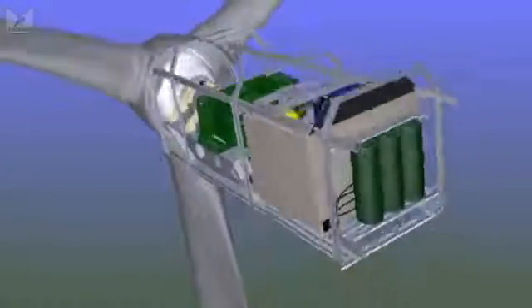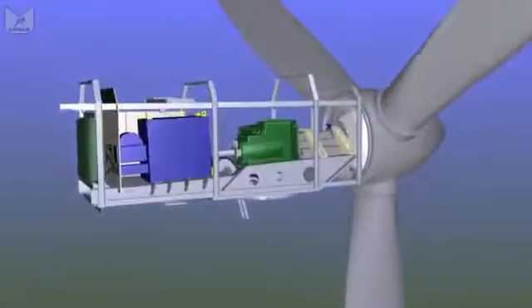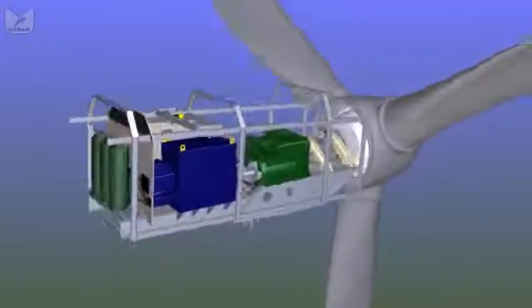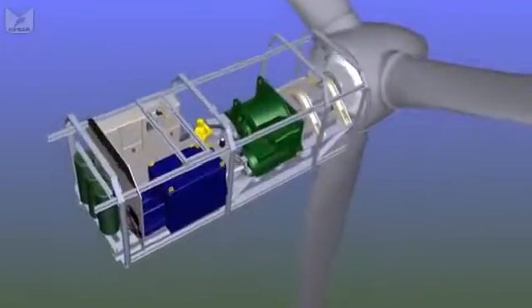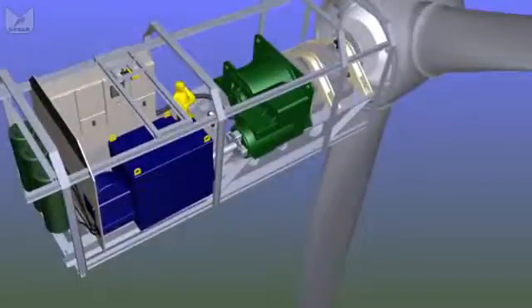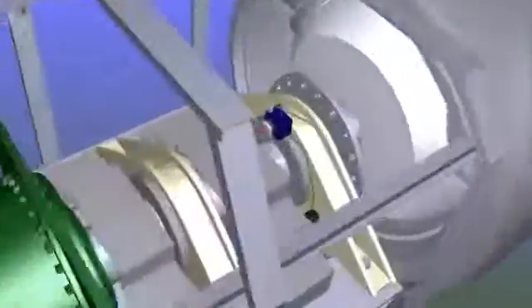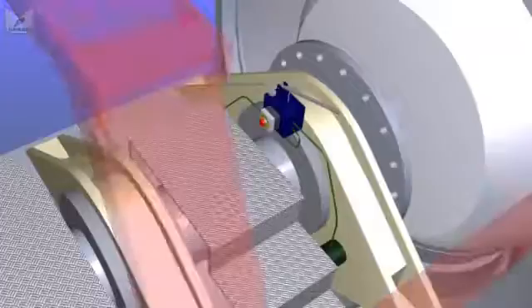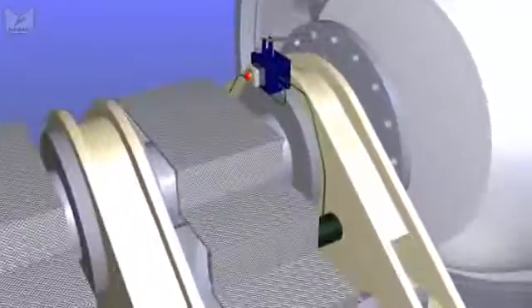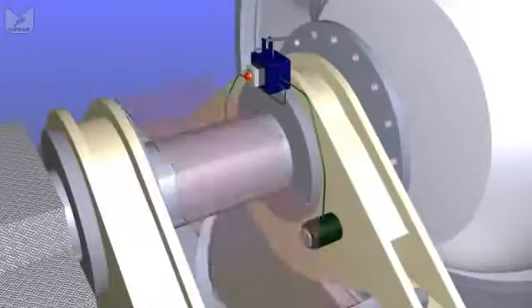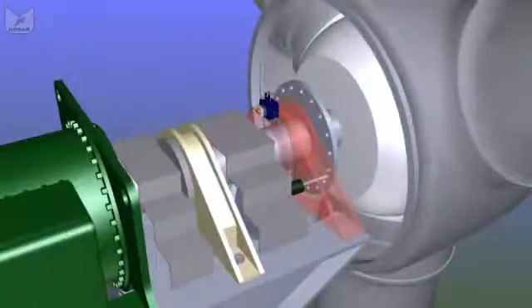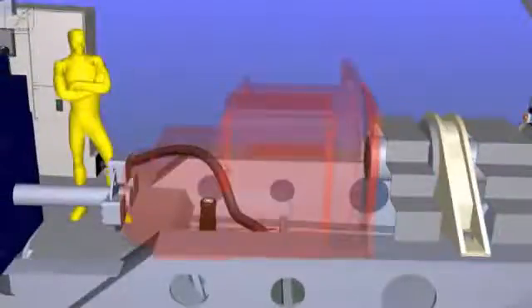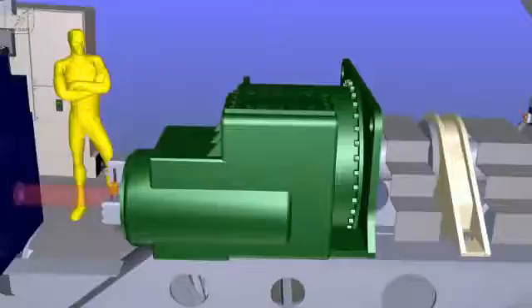If we take the skin off the box, inside we have the same kind of components we had before, they're just bigger and there's a little bit more room. The only additional component up here is those three green cylinders at the back - that's our high voltage transformer. At the very front of the nacelle we have a couple of bearings which support the main shaft, which is a hollow tube 50 to 70 centimeters in diameter. It's hollow so that we can get electrical cables in through this main shaft into the hub to drive all the control systems inside the hub. We have a couple of pins on the first bearing that lock the main rotor in position if we need to access the hub. Our main shaft drives our gearbox, which is mounted centrally because it's often the heaviest component.